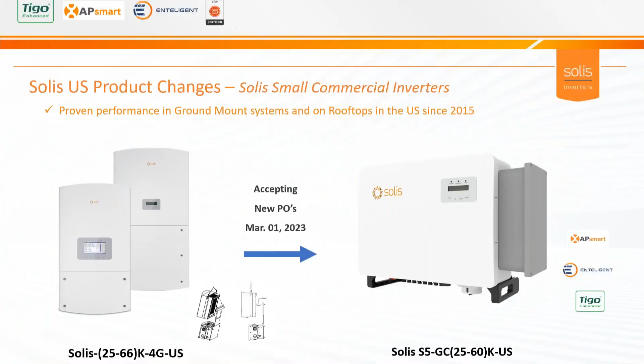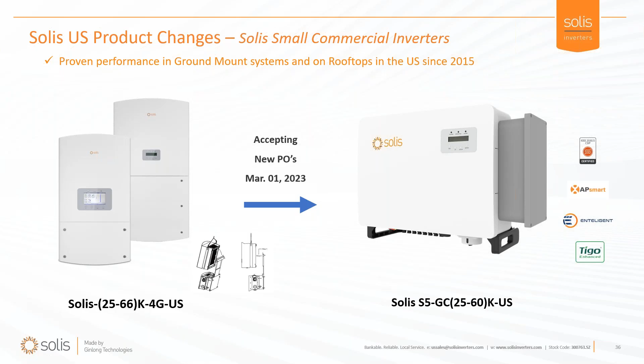In the old days, this is what we have available today, the 25 to 66K product. One of the cool things about it was the capability to separate the wire box from the power head, so you could do swap outs quite easily that way. With the new inverter, all the solar strings go right into the bottom with MC4 connections, and the new AC connections are in that big wire box on the side, which you can remove entirely. So you just unplug from the bottom, remove the AC wire box, and plug right in—giving you that real fast swappability to keep the uptime going on your commercial systems.